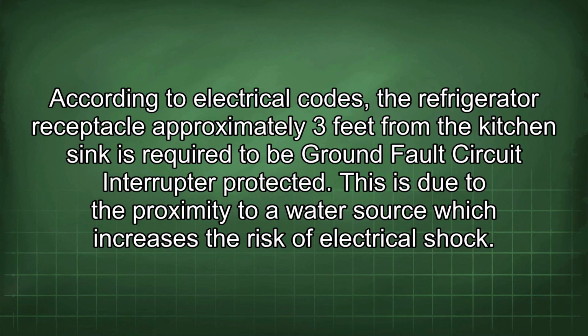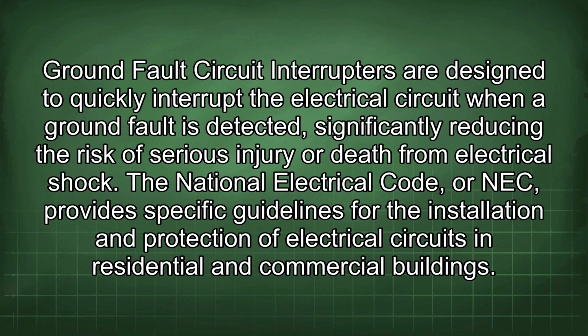According to electrical codes, the refrigerator receptacle approximately 3 feet from the kitchen sink is required to be ground fault circuit interrupter protected. This is due to the proximity to a water source, which increases the risk of electrical shock. Ground fault circuit interrupters are designed to quickly interrupt the electrical circuit when a ground fault is detected, significantly reducing the risk of serious injury or death from electrical shock.